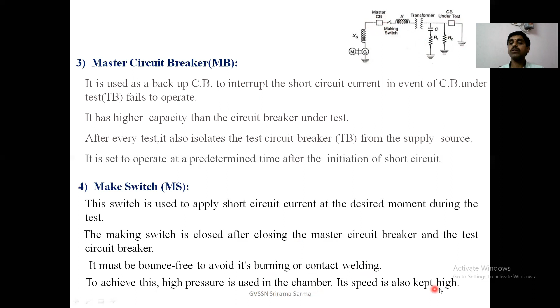What is a make switch? This switch is used to apply short circuit current at the desired moment during the test. So this is closed to supply short circuit current to the breaker. The make switch is closed after closing the master circuit breaker and test circuit breaker. It must be bounce free to avoid burning or contact welding. To achieve this, high pressure is used in the chamber. Its speed is also kept high.